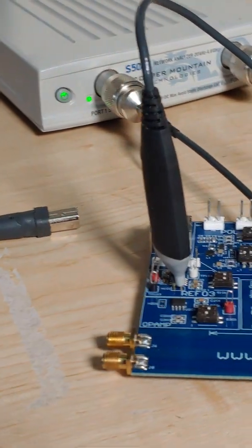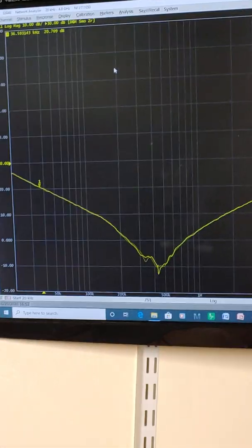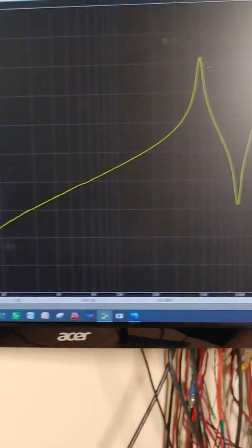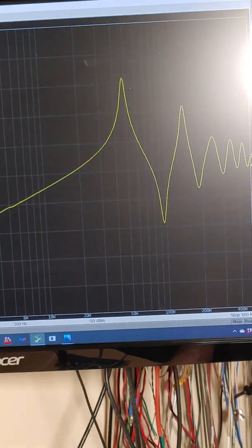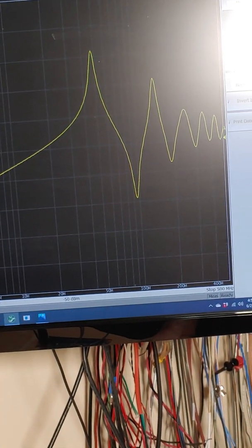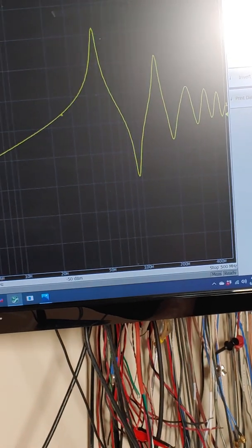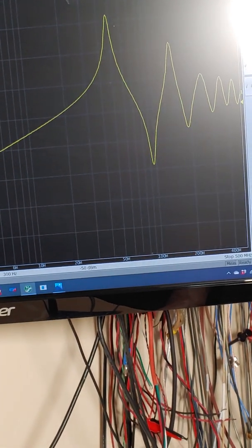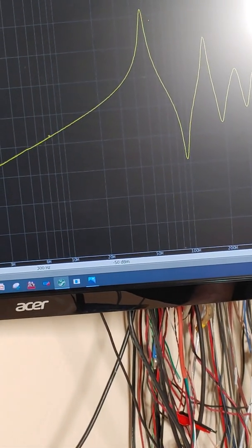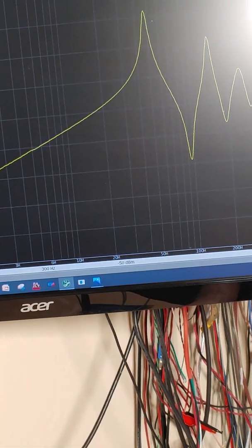The power cable is sitting over here, so it's not connected. And if we look at the impedance, there's no peak at the low-frequency end, but there are peaks at the high-frequency end, and that's without power applied, so those are passive. I'm going to display, and I'm going to put that data to memory, so now we've saved the off state.